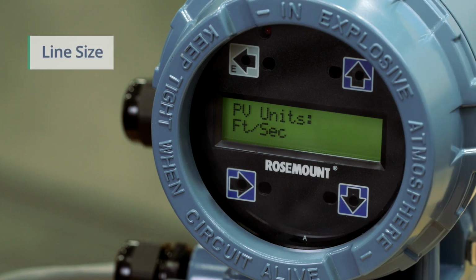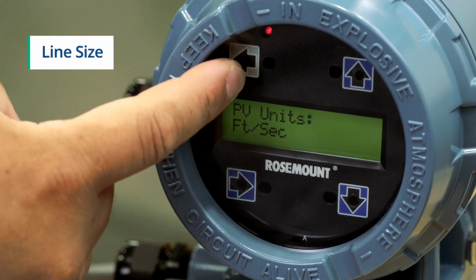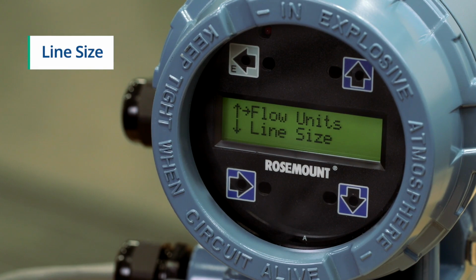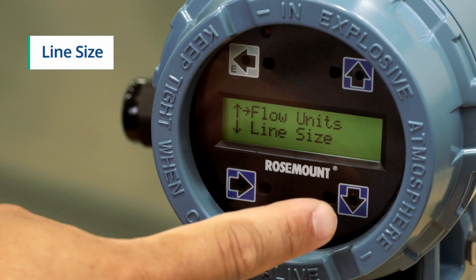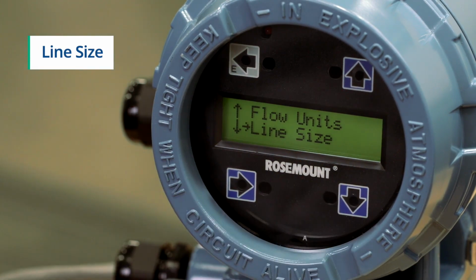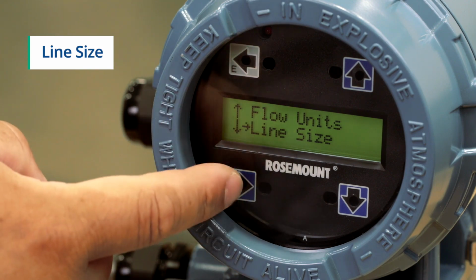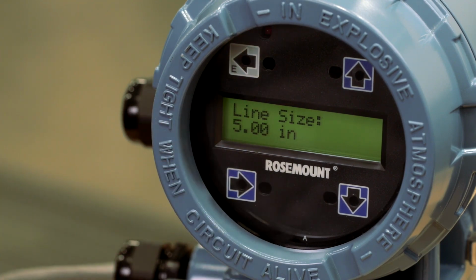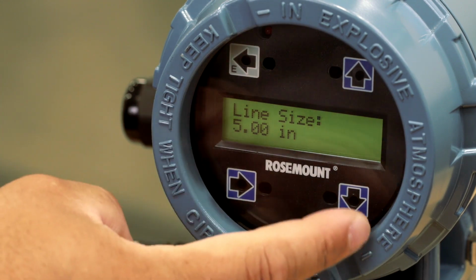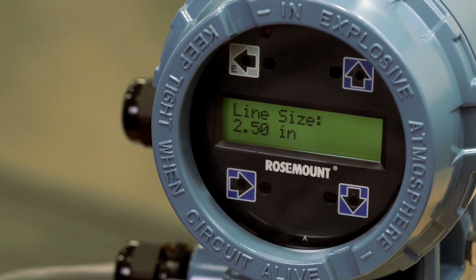To input the line size, press the E button to navigate back to the basic setup screen. Then press the down arrow to scroll through the menu options, and press the right arrow to select line size. Press the up or down arrows to increase or decrease the sensor line size to the next value. Press the E button to select the sensor line size. Press the E button again to save your selection.